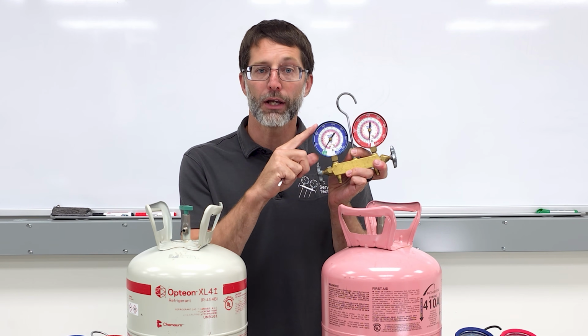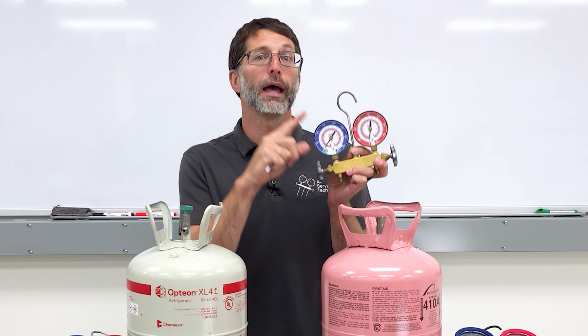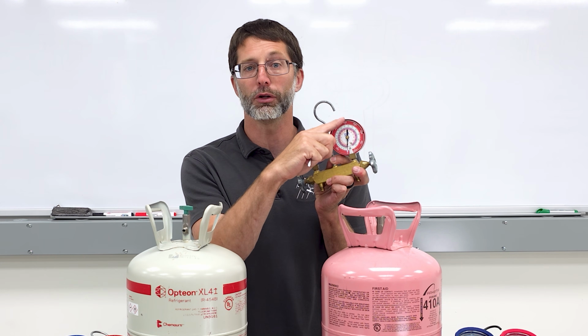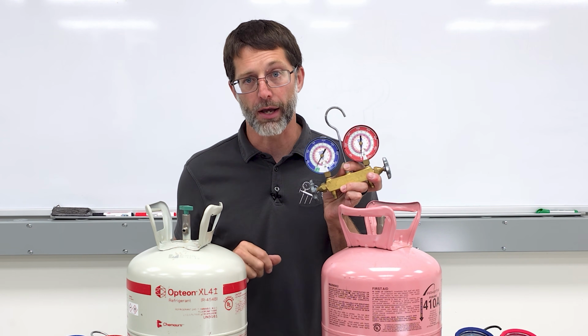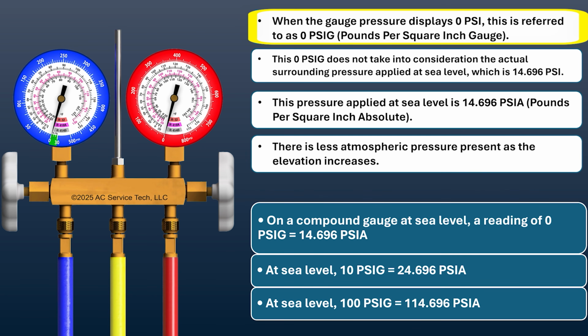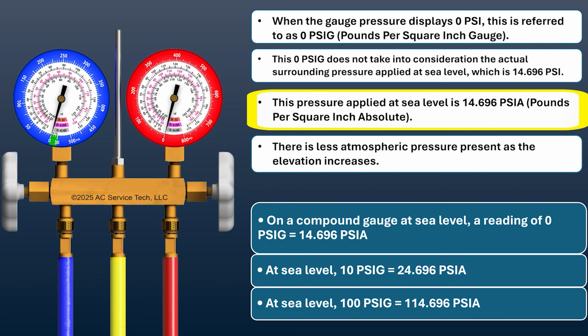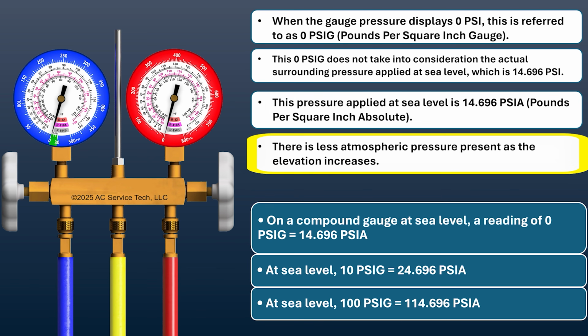A blue compound gauge measures pressure above 0 psi and below 0 psi, but a red gauge only measures pressure above 0 psi. When a gauge pressure displays 0 psi, this is referred to as 0 psig. That means pounds per square inch gauge. This 0 psig does not take into consideration the actual surrounding pressure applied at sea level, which is 14.696 psi. This pressure applied at sea level is 14.696 psia, pounds per square inch absolute. There is less atmospheric pressure present as the elevation increases.